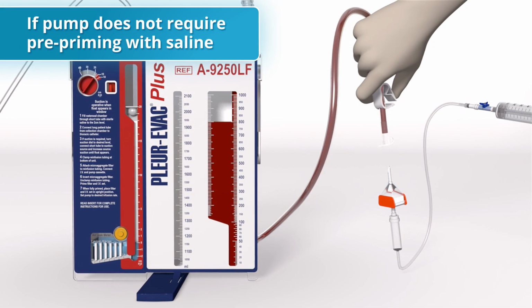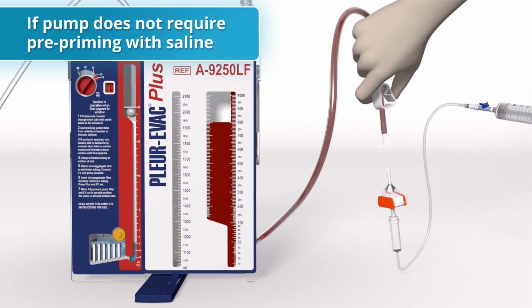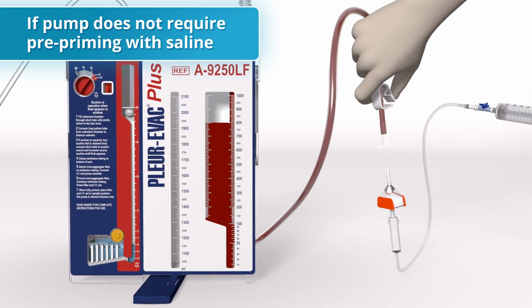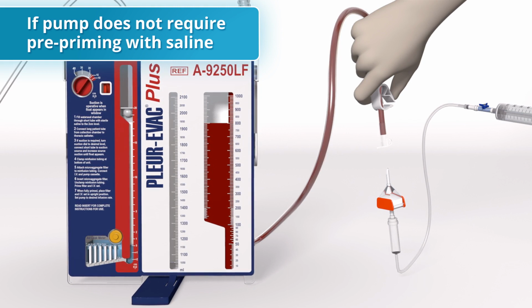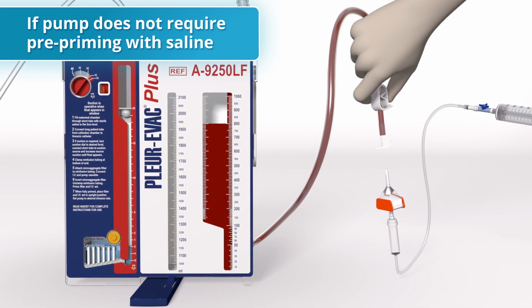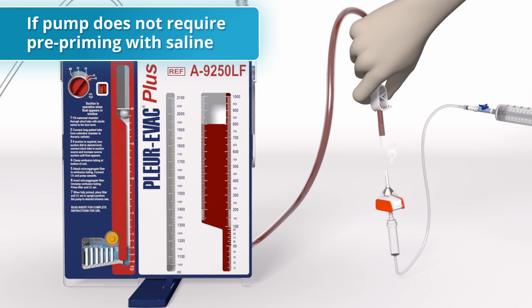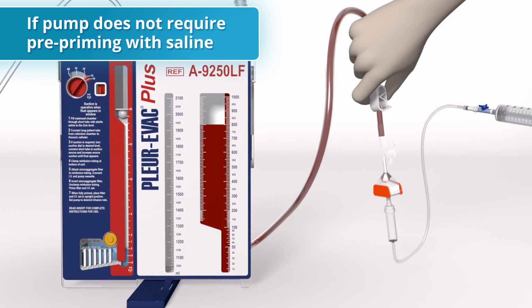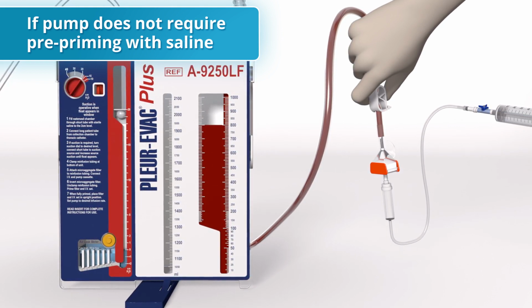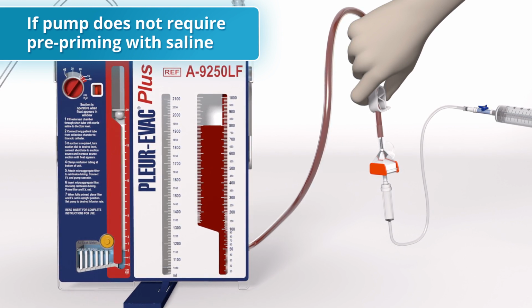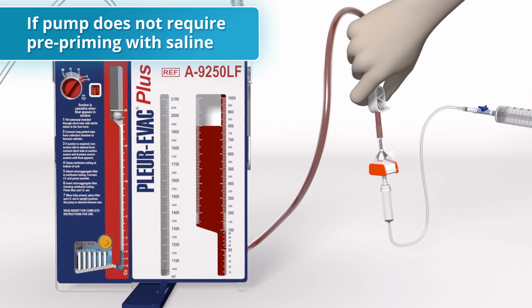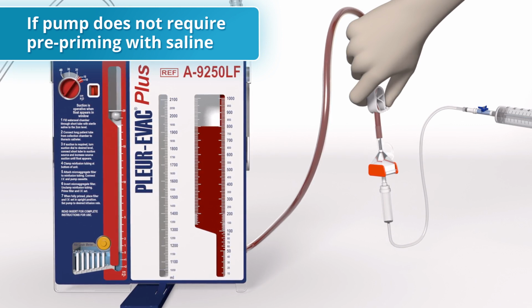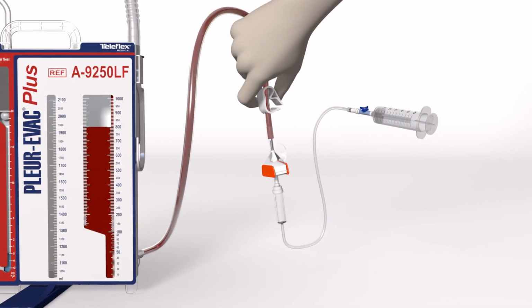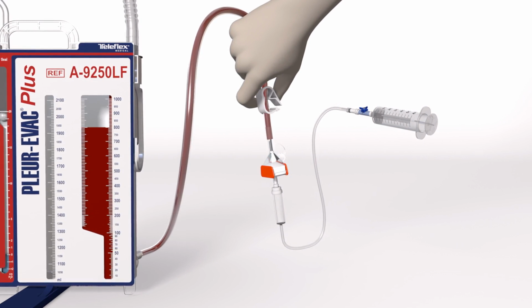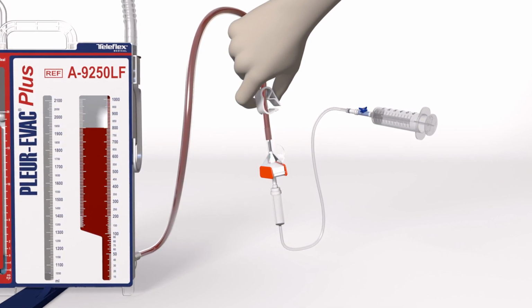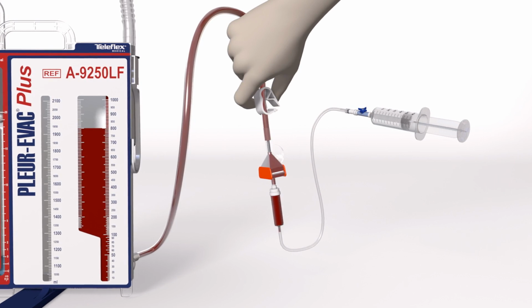If the infusion pump does not require pre-priming with saline, priming will be done with blood following milking of the reinfusion tubing, as previously discussed. With the clamp in the closed position, remove the tethered cap from the exit port of the reinfusion tubing and spike it with the microaggregate filter and administration set. The set should be positioned in a spike-up orientation to allow for priming with blood. The clamp should now be reopened. Finally, you will begin priming the microaggregate filter and administration set with blood using the IV pump or a 60 cc syringe and stopcock.